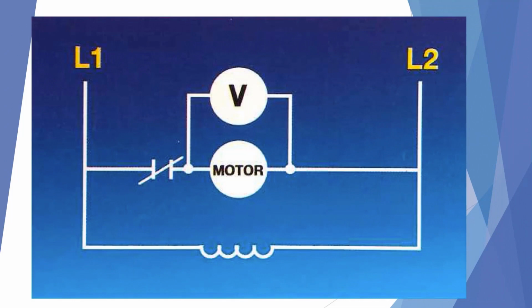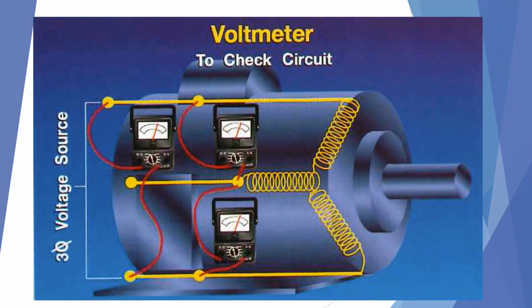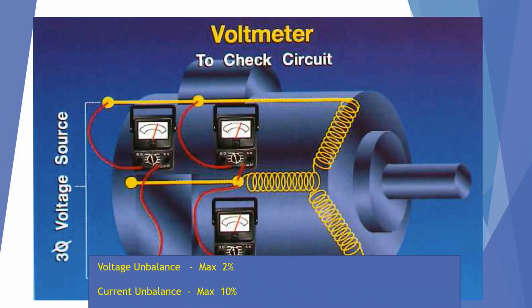The next step would then be to make sure that the correct voltage is being supplied to the component that is not working. If you have voltage being supplied to a motor, for example, and the motor is not running, the problem is most likely that the motor is bad and is not able to turn or run with the voltage applied to it. With a voltmeter, we want to make sure that the proper voltage is being supplied to each leg of the motor. And you also want to check for voltage unbalance, which is a maximum of 2%, and current unbalance, which is a maximum of 10%. Exceeding these limits will cause the motor to run hot and will result in motor failure.